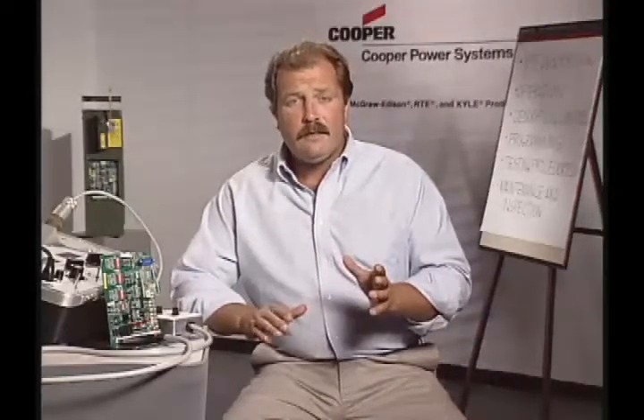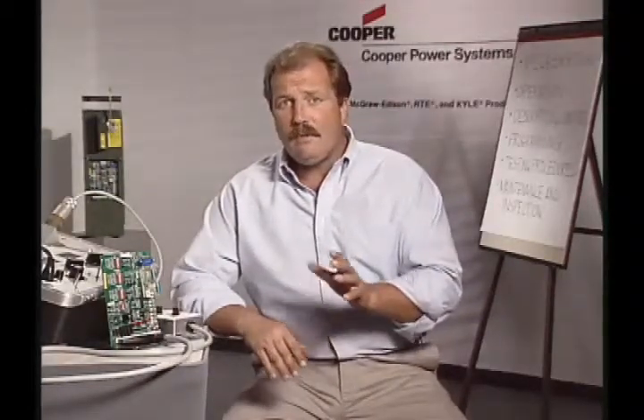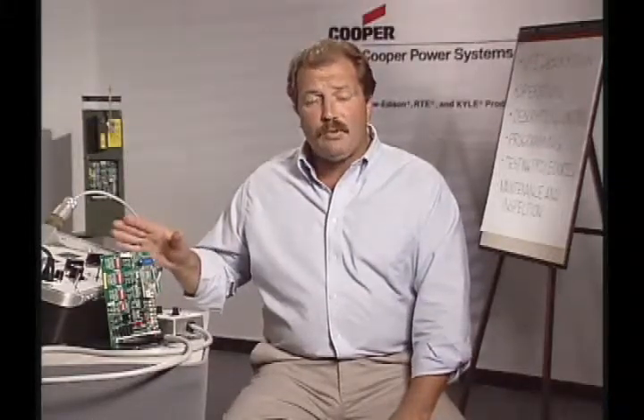Periodic tests of minimum trip and time delay can be conducted to verify proper operation of the tri-phase control. The control can be field tested in its housing or tested in a suitably equipped service facility. We'll test the control with the Kyle ETC electronic trip control tester.